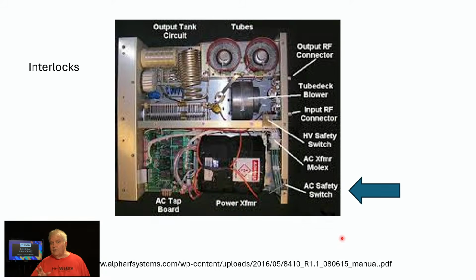So if you're going to do troubleshooting on amplifiers like this, again, you should be comfortable with this. You should be qualified. You should have knowledge about this. You can bypass the interlock in order to make voltage tests and things like that. But you don't want to, as a rule, bypass the interlock and just leave it bypassed. No, they're there for a reason.